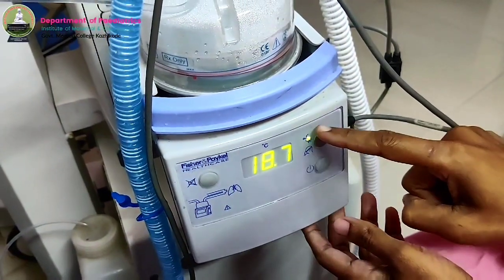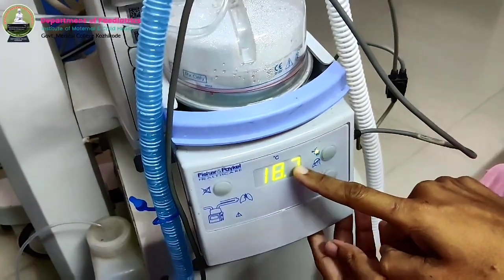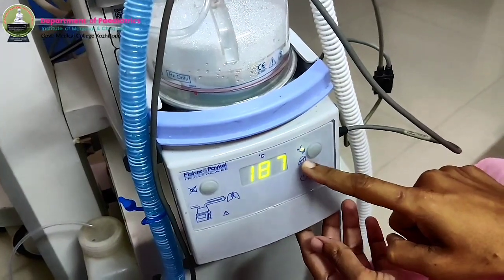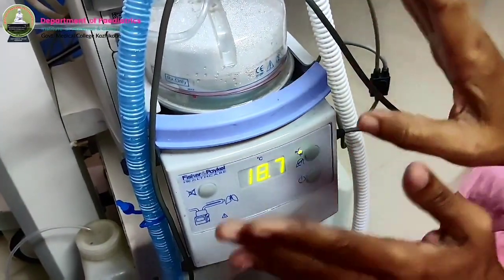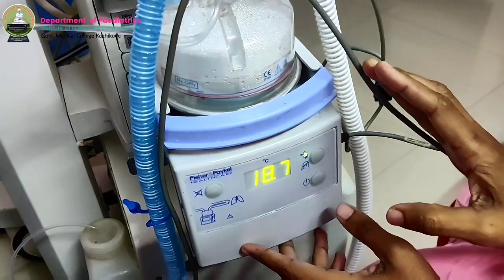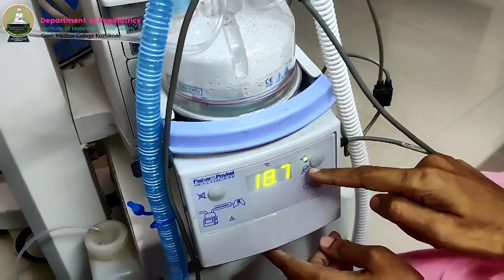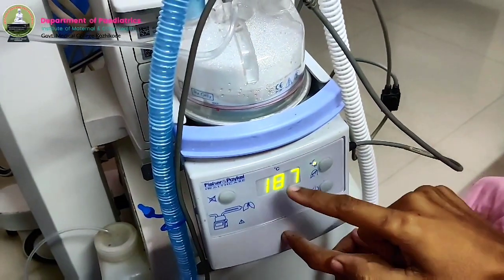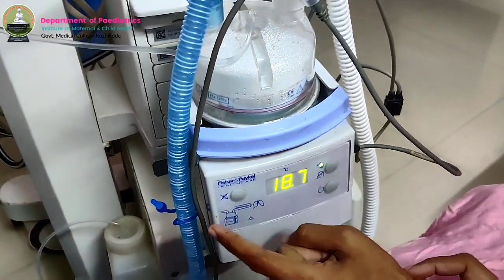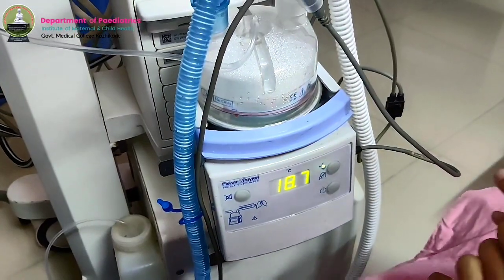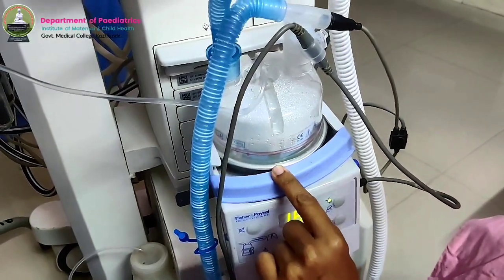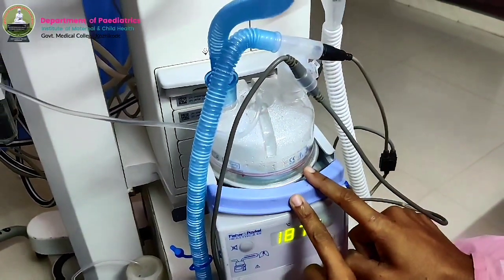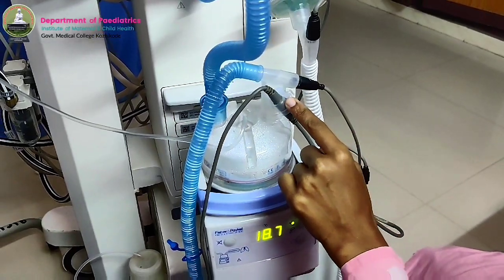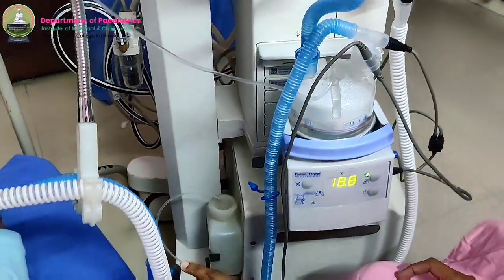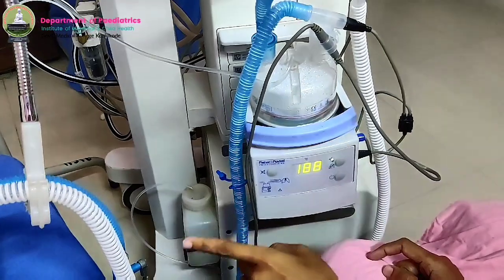So in that, the temperature set will be 37 degree. In non-invasive, it is 34 degree. So the machine itself controls the temperature by the mode we select. So here, 3 temperature measuring points are there. One is at the base of this heating heater. Another one is near the humidifier. Third one is near the patient. So 3 sensors are there, and that will be shown in this picture.